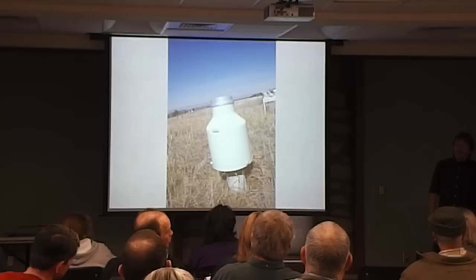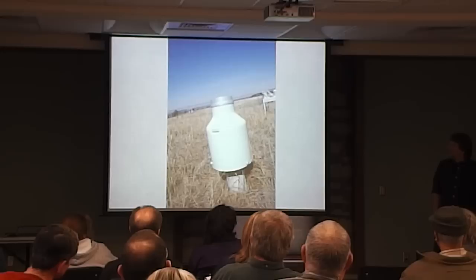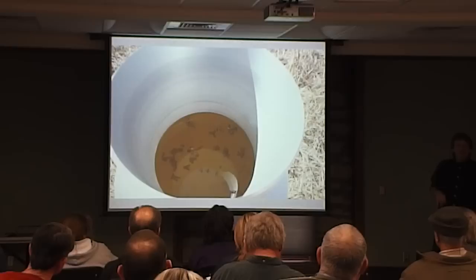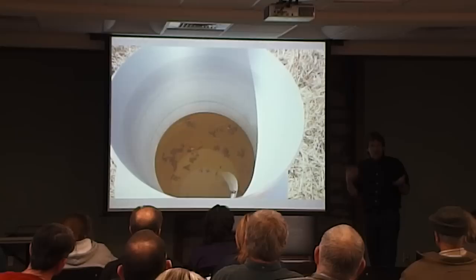When a truck bags one of these, you're not happy. We're currently supplementing the Belfort rain gauges with this vibrating wire gauge at the headquarters area — that's the only place we have one. You do collect bugs in there, but we don't empty this one regularly, so these things have probably been collecting for a while. We wouldn't use this for chemical concentrations, just for amounts.